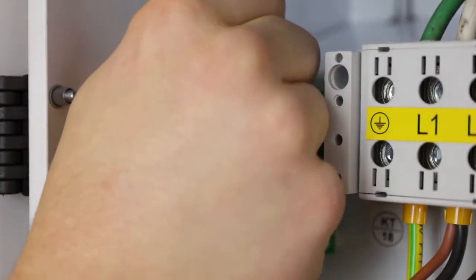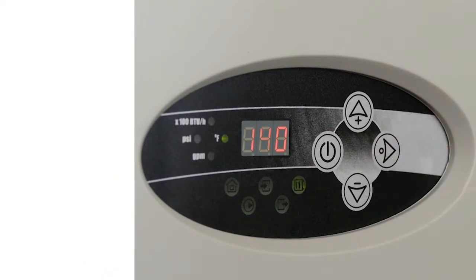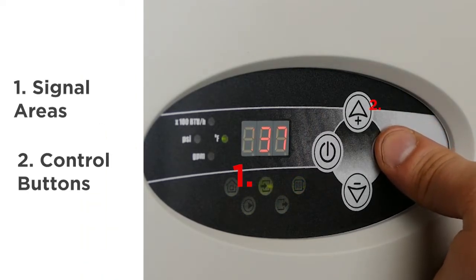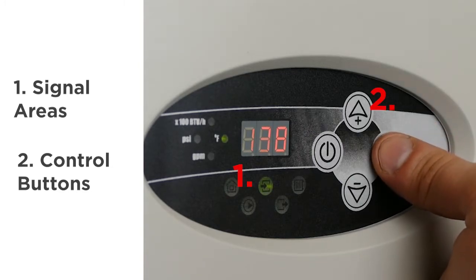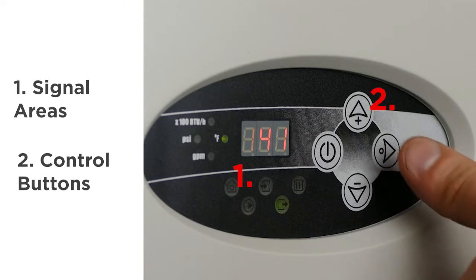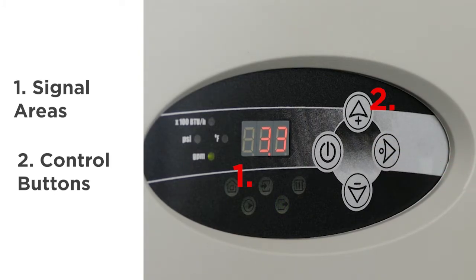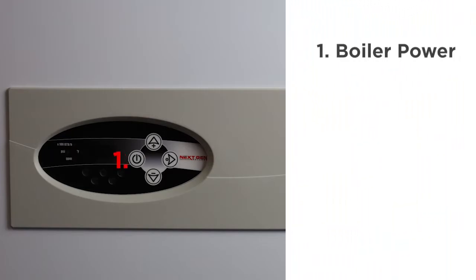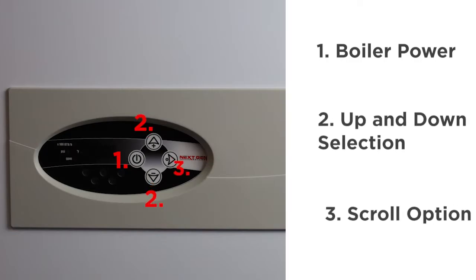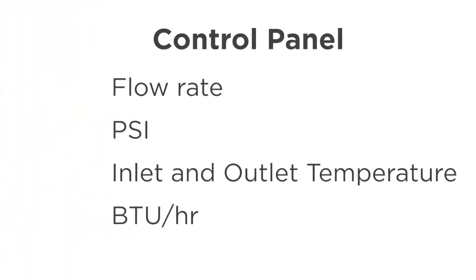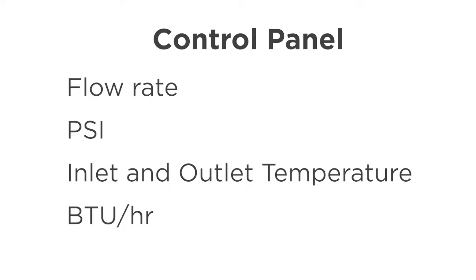The control panel consists of 2 working areas, the signaling area and control buttons. Utilize the right arrow to scroll through the parameters of the boiler. If no button is pushed, the boiler will automatically switch to the main view after 1 minute. The 4 buttons to familiarize yourself with are the boiler power, up and down selection, and the scroll option. The control panel allows you to identify the flow rate, PSI, inlet and outlet temperature, and the BTU per hour of the boiler at any given time. It can also aid in identifying faults with the boiler by displaying fault codes.